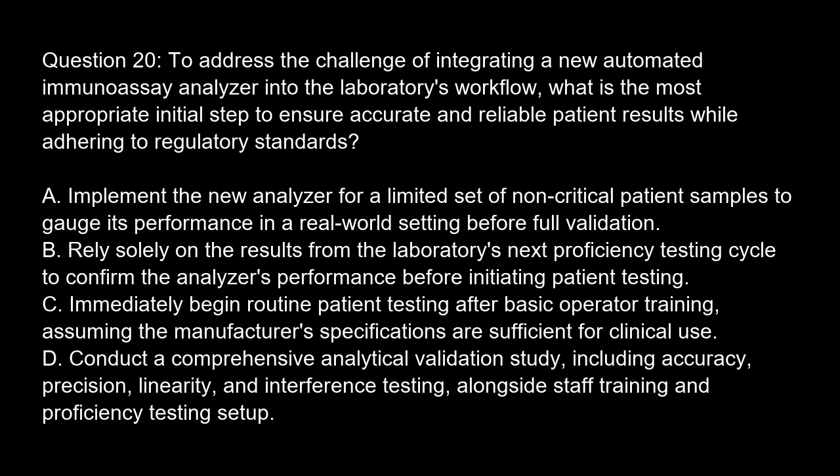Question 20. To address the challenge of integrating a new automated immunoassay analyzer into the laboratory's workflow, what is the most appropriate initial step to ensure accurate and reliable patient results while adhering to regulatory standards? Option A. Implement the new analyzer for a limited set of non-critical patient samples to gauge its performance in a real-world setting before full validation.